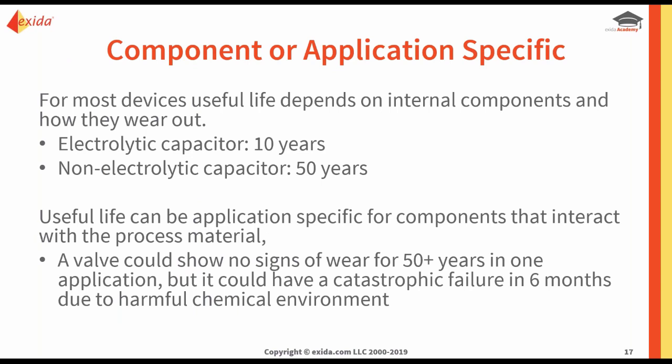So for most devices, the useful life depends on the internal components and how those components wear out. So for instance, for an electrolytic capacitor, your useful life might be 10 years, but with a non-electrolytic capacitor, your useful life could be extended to 50 years. So a lot of it depends on the internal components of the device, how they're being used and how they wear out.